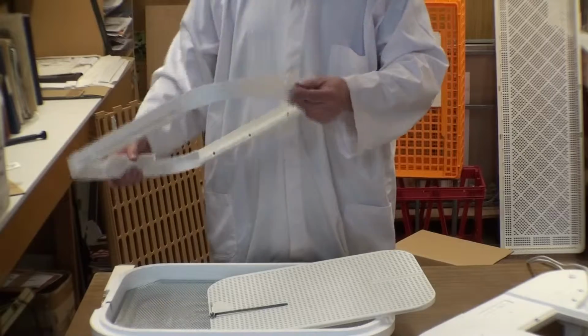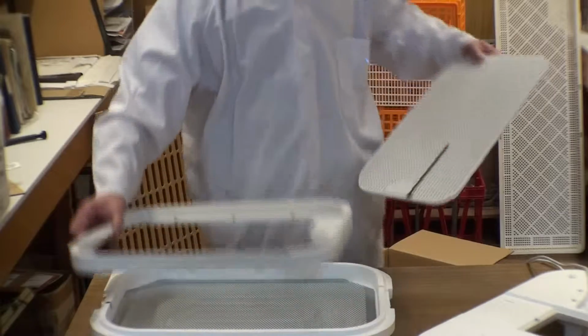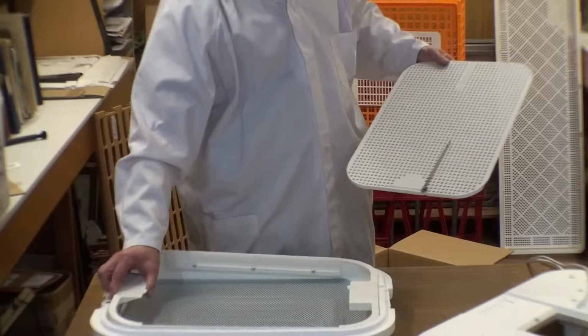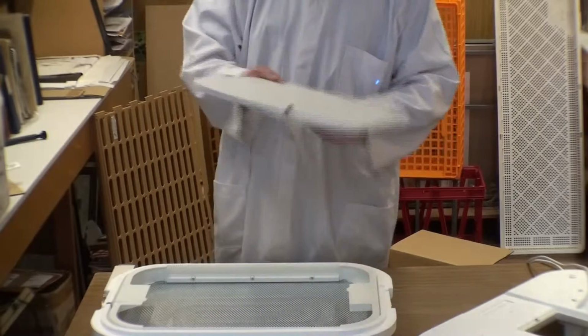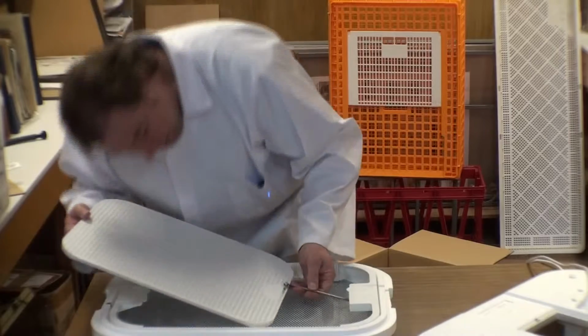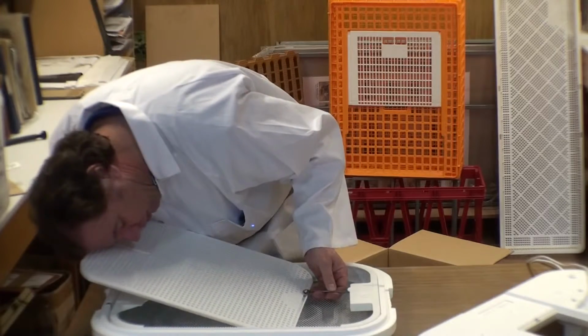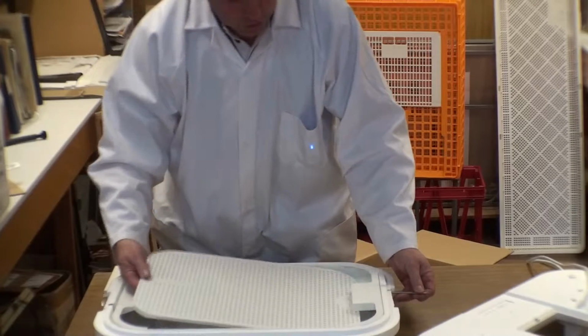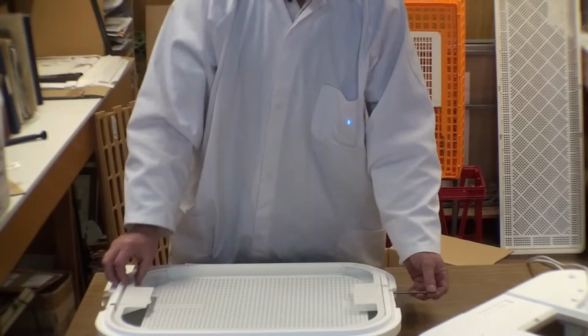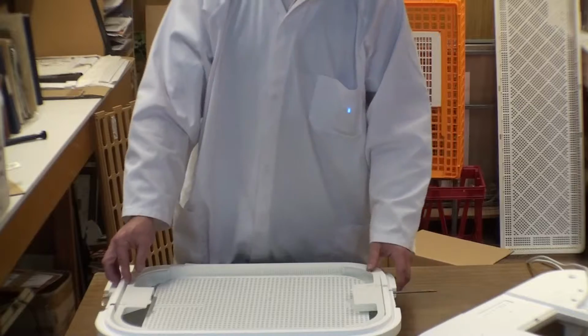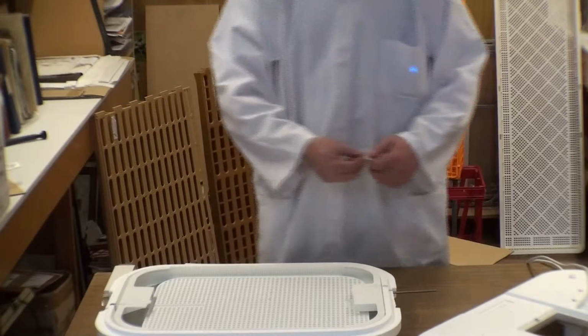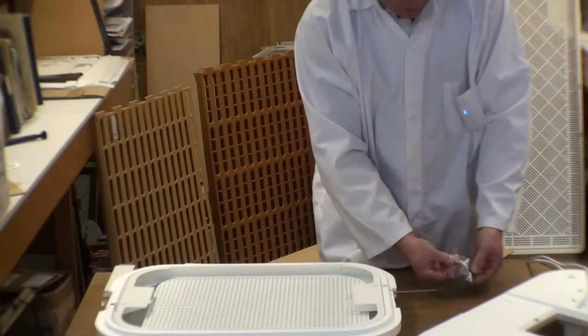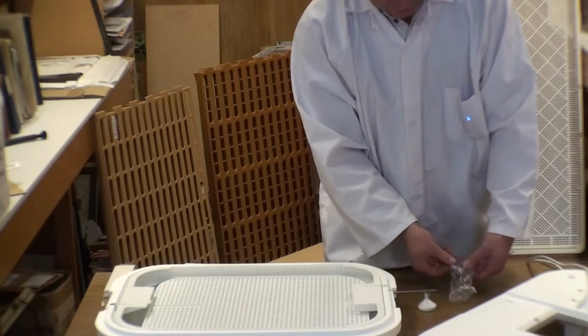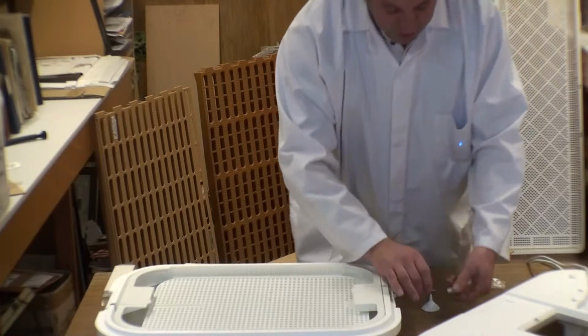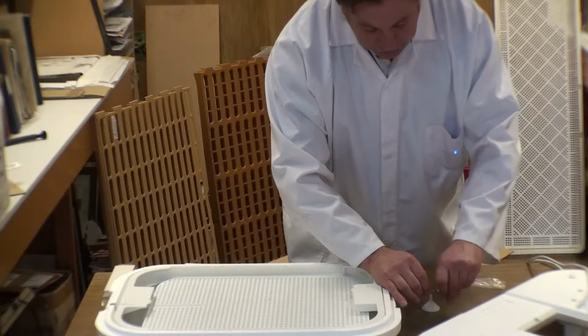Now we're going to place that tray with a little hole matching up with the slot in the side of the incubator. We're then going to take the moving tray with a push rod and place the push rod through the little hole into the outside world. Now we've placed the tray inside so the tray can move backwards and forwards in the incubator. We'll get the little knob and we'll place the knob on the end of the control shaft. And so we'll screw that knob on the end of the control shaft so that we've got something nice to pull it backwards and forwards with.